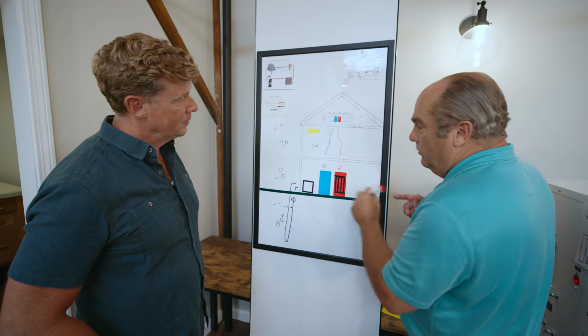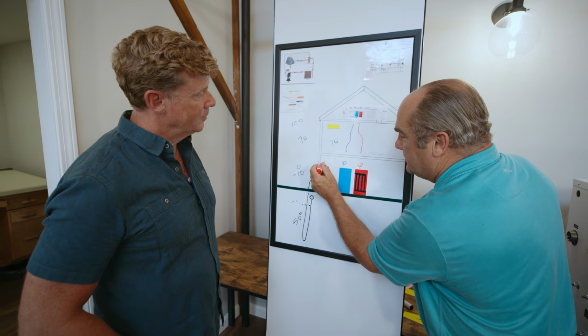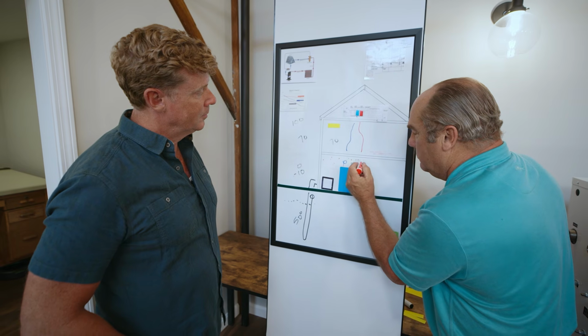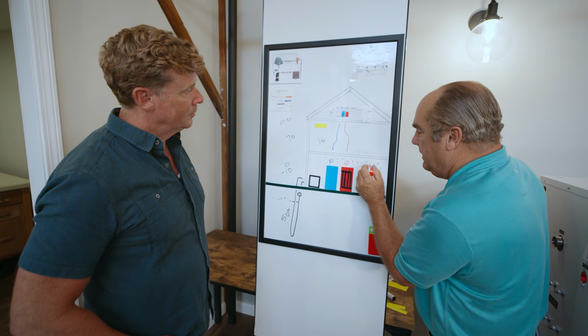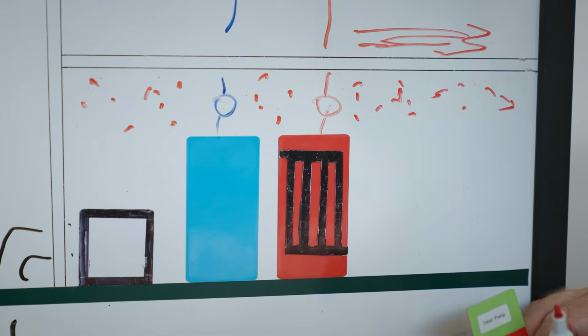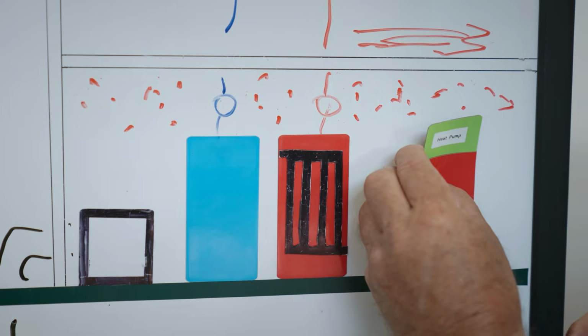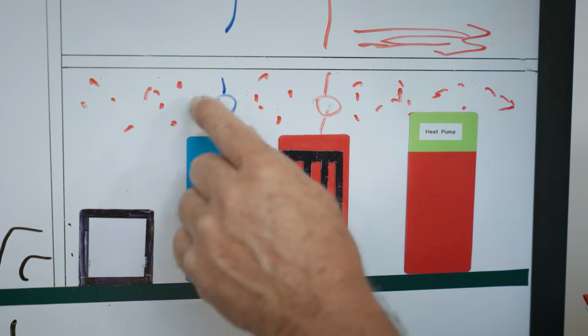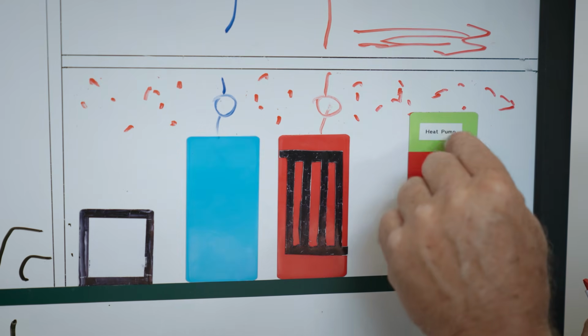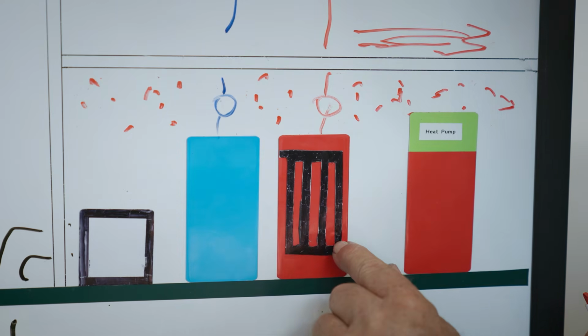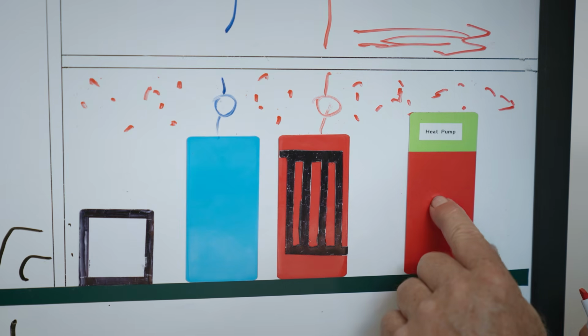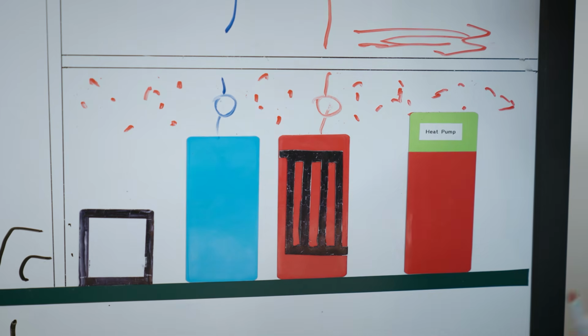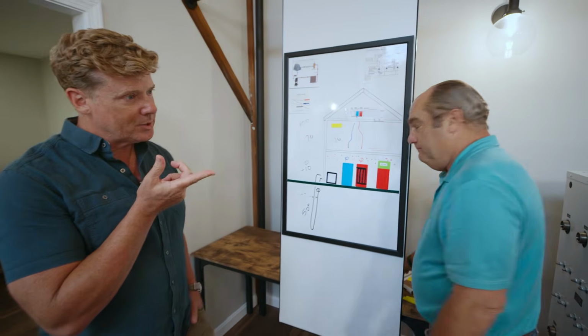But we also have all these pumps and all the equipment. So in the mechanical room, there's always temperature in here. So now what we're going to do is add the last component, which is a heat pump water heater that will find the heat that's in that air, transfer it down into this tank, which will act as a reserve tank and help in the production of domestic hot water. Wow. And so the equipment is what we're looking at here?